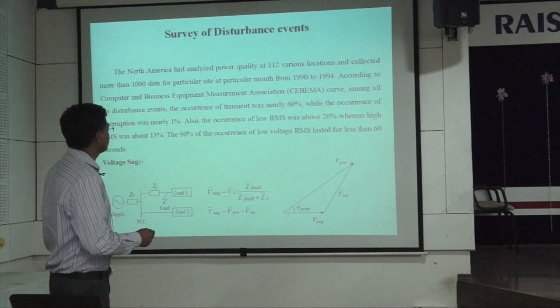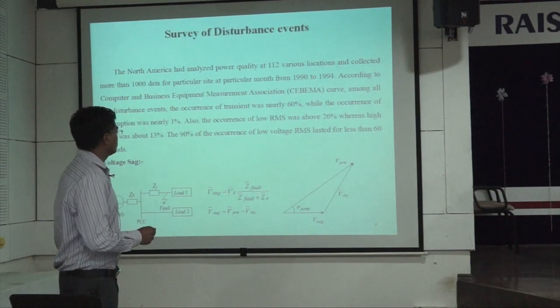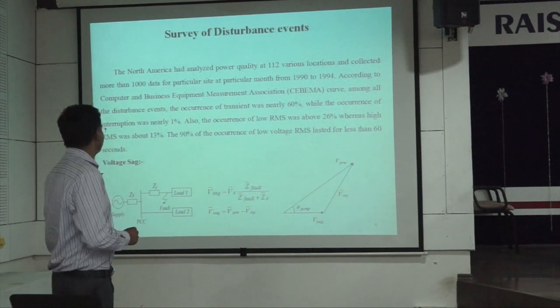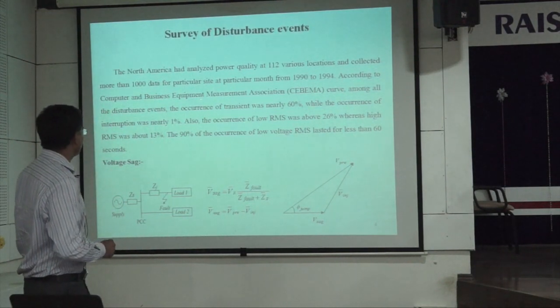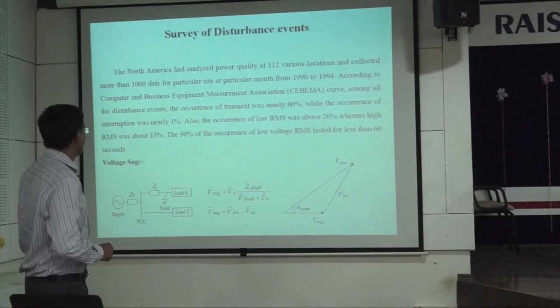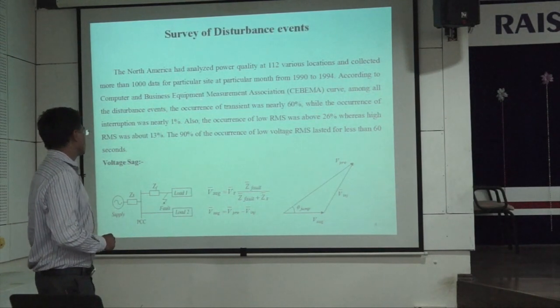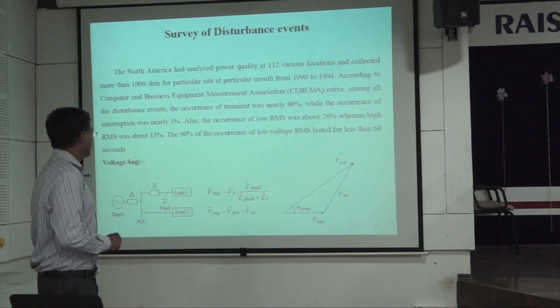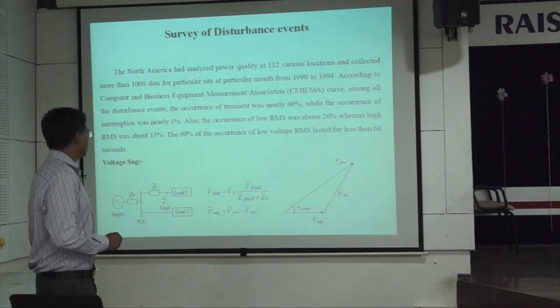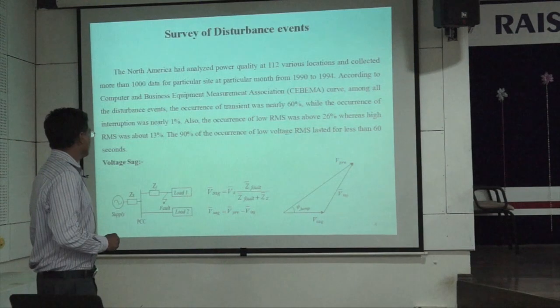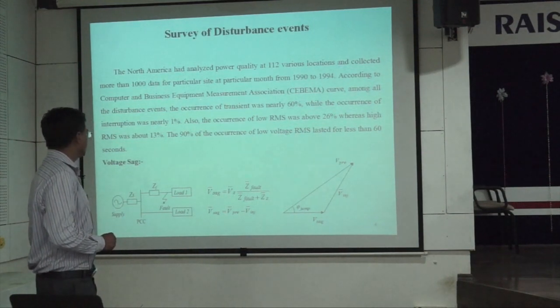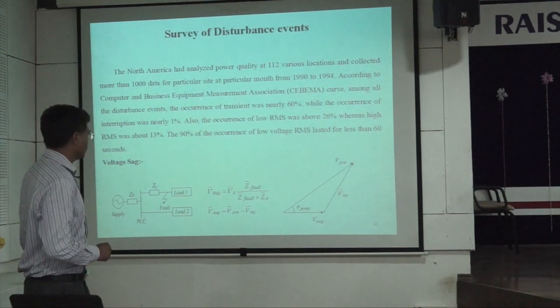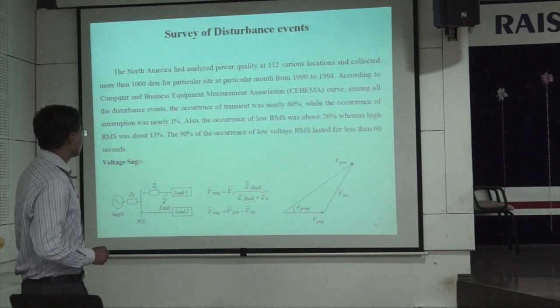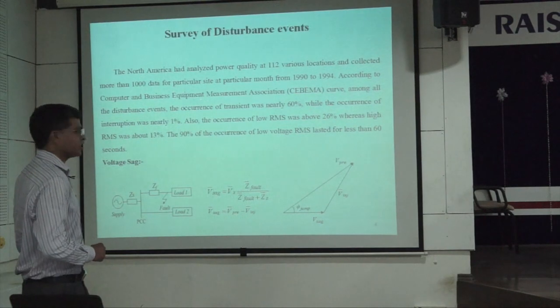Now as the RMS decreases, there is a low RMS of about 26%. So whenever there is a fault at one of the loads, there is a decrease in the voltage at the other load. That is called the voltage sag. Voltage sag is characterized by these two equations, where ZF is the fault impedance and ZS is the source impedance. So with the decrease in the source voltage, there is a decrease in the voltage level at the load side. So we have to inject the voltage at a particular angle so that we maintain the voltage at the desired reference value at the load side.